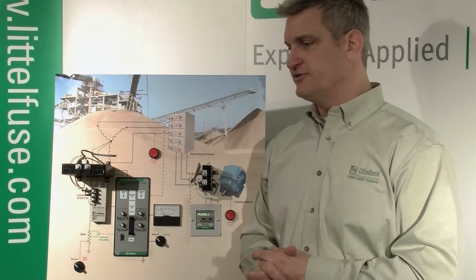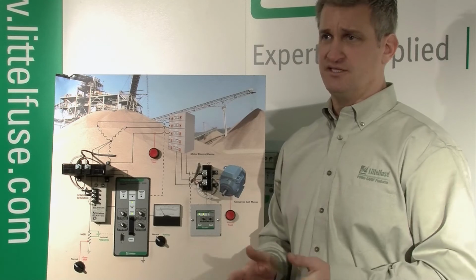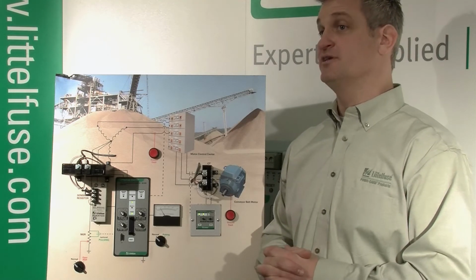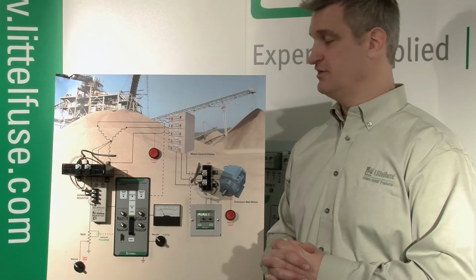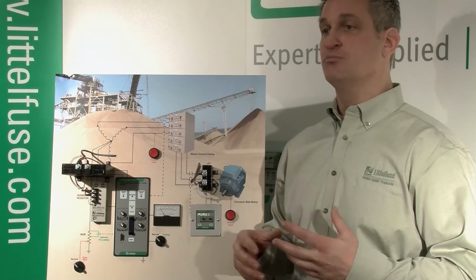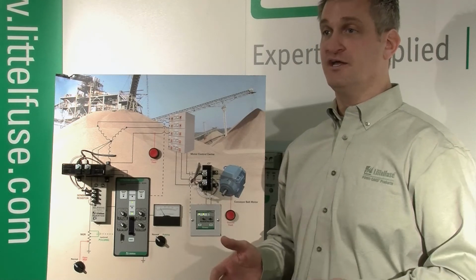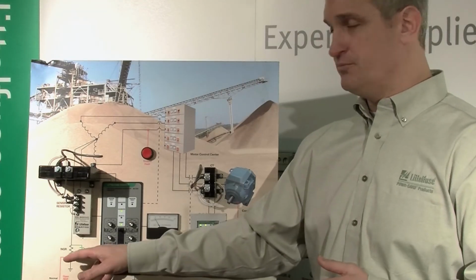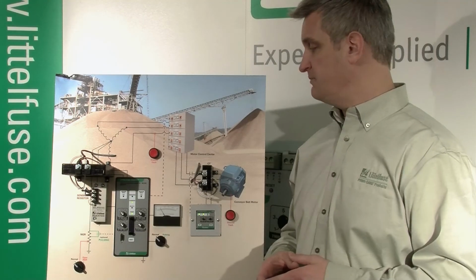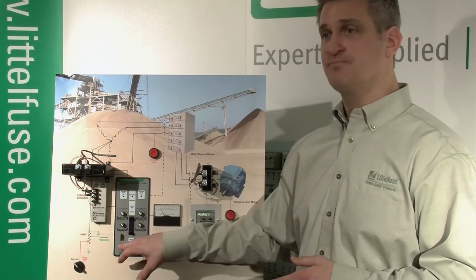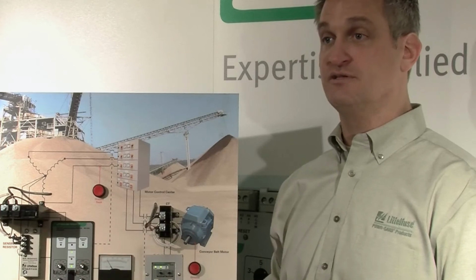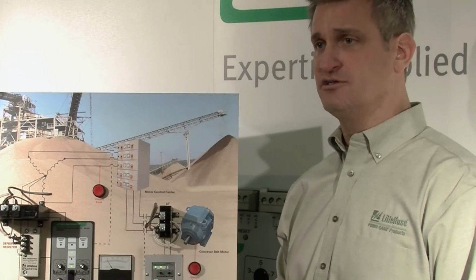We had a customer of ours, a textile company down in the southeast. They had resistance grounding, but it had been in place for 30-plus years. They were experiencing a lot of blown motors throughout the facility and had no idea why. They tracked it down to an open NGR. They called us, and they now have installed our 330 in all their systems. They told us they've saved a lot of motors by installing the 330.